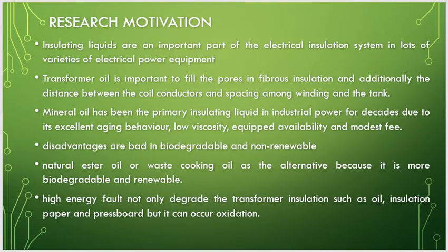Then my research motivation: insulating liquids are an important part of the electrical insulation system in a large variety of electrical power equipment. Transformer oil is important to fill the pores in fibrous insulation, and additionally the distance between the coil conductor and the spacing among the winding and the tank.